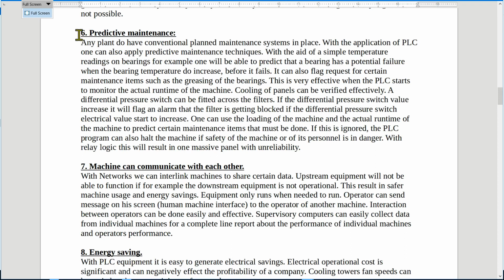And point 6, with the aid of a PLC, we can even apply predictive maintenance techniques. Now, any plant does have conventional maintenance systems in place. With the application of a PLC, one can apply more advanced predictive maintenance techniques. For example, with the aid of simple temperature readings on bearings, one will be able to predict that the bearing has a potential failure when this bearing temperature starts to increase. And this happens before the bearing fails. So you will become aware of a maintenance challenge before it actually halts the machine.